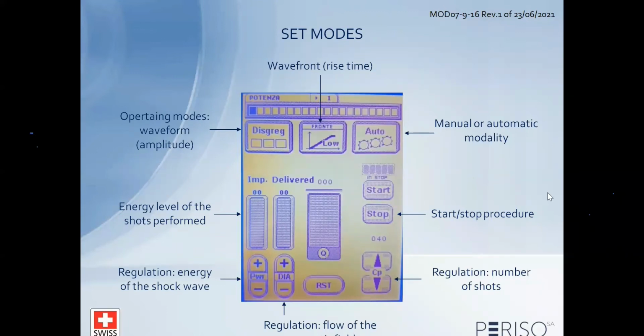Here you can see the screen with the set modes of the device. As you can see, you can change the waveform of the shock wave, so the amplitude and the shape of the shock waves. You can change the wavefront, the rise time, so you can modulate the shock waves in time.